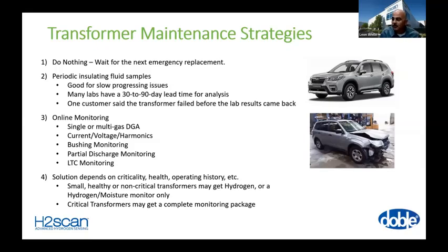Usually when people start doing monitoring, the DGA monitor is the first thing they'll put on, because looking at the insulating fluid and when gases are generated in that fluid is a good indicator, just like a blood test on yourself is good to get an understanding of how healthy you are. Looking at the gases in the transformer oil or transformer fluid is very important. And then of course, as the criticality increases, or you may have unhealthy transformers on your system, whatever the case may be, there are times when you want to go to the multi-gas systems that do partial discharge and bushing monitoring and so forth. And again, the vendors can provide a lot of recommendations on what you should be putting on a particular transformer based on what bushings are in there and what type of load tap changer, if it has one, and so forth.